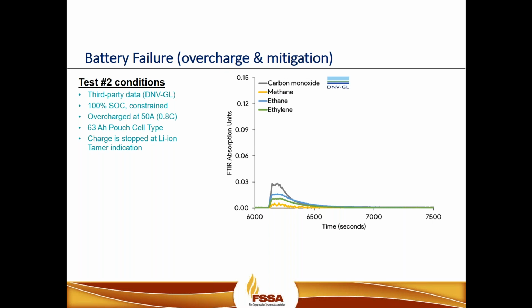As you can see here in the graph, traditional type sensors, and we'll show in the next graph the temperature associated with that, cannot detect at lower levels of off-gassing, and the battery management system may be challenged to detect an overcharging or overheating event because of a lack of thermal temperature increase. So waiting for a ppm type detector may be too late. Say if it were detecting at 25 parts per million, for example. That's primarily because the LEL detectors and the technology on the market today have what's known as a deadband factor. Deadband factor is the threshold at which the technologies have the ability to detect. And again, they really don't have the ability to go to those lower level limits that are required for detection.